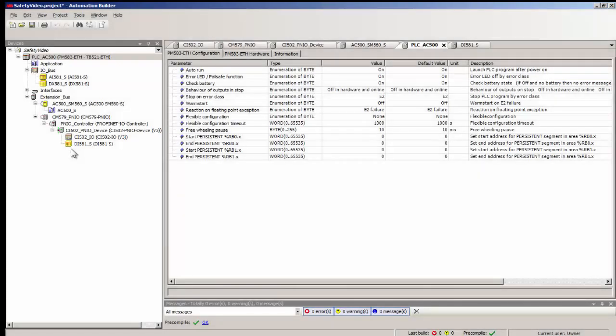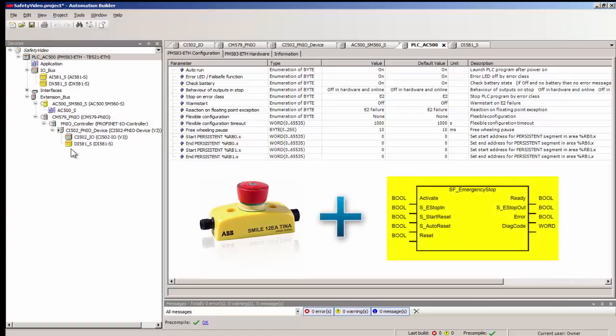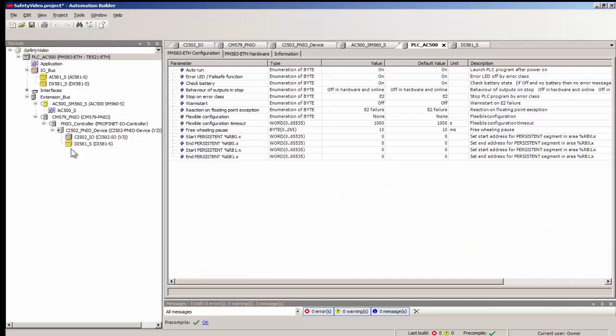We present how to program a SIL 3 emergency stop function with the help of a PLC open standard library function block. Please note that this is merely an example project that would just meet the requirements of stop category 0.